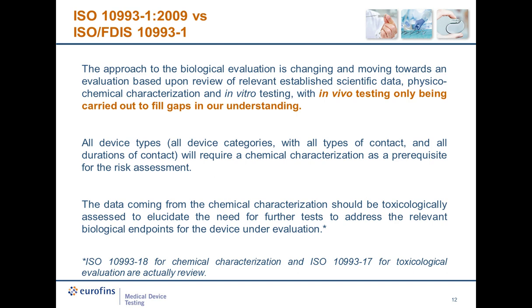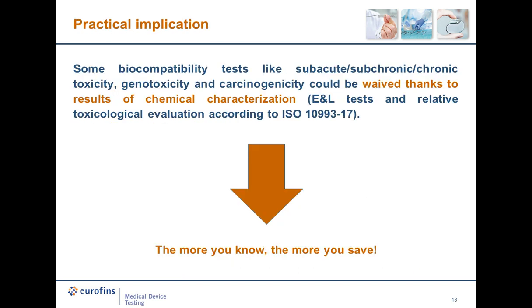The approach to the biological evaluation is therefore changing and moving towards an evaluation based upon review of relevant available data, physical chemical characterization, and in vitro testing, with in vivo testing only being carried out to fill gaps in our understanding. All device types will require a chemical characterization as a starting point for the risk assessment. The data coming from the chemical characterization should then be toxicologically assessed to elucidate the need for further tests to address the safety of the device.